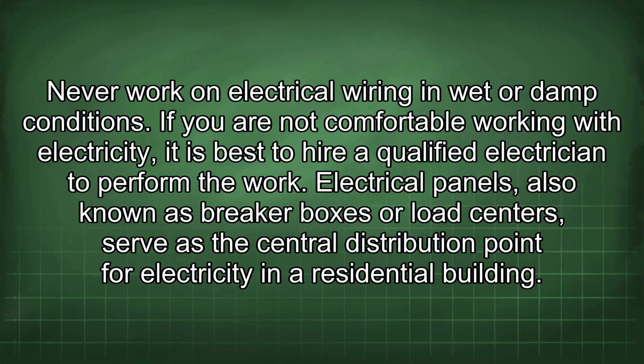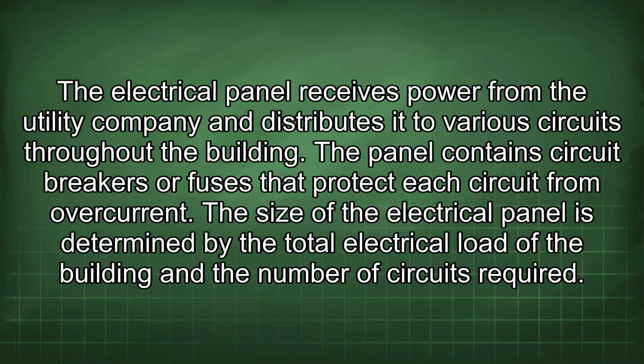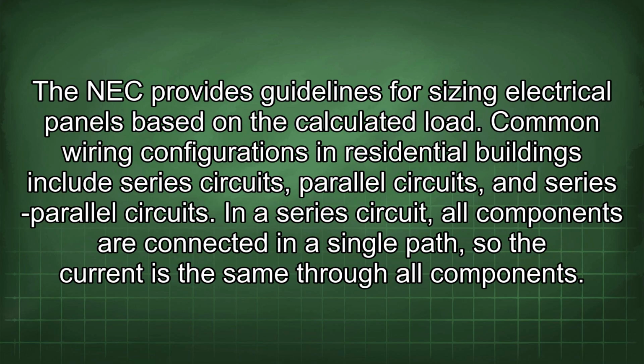Electrical panels, also known as breaker boxes or load centers, serve as the central distribution point for electricity in a residential building. The electrical panel receives power from the utility company and distributes it to various circuits throughout the building. The panel contains circuit breakers or fuses that protect each circuit from overcurrent. The size of the electrical panel is determined by the total electrical load of the building and the number of circuits required. The NEC provides guidelines for sizing electrical panels based on the calculated load.